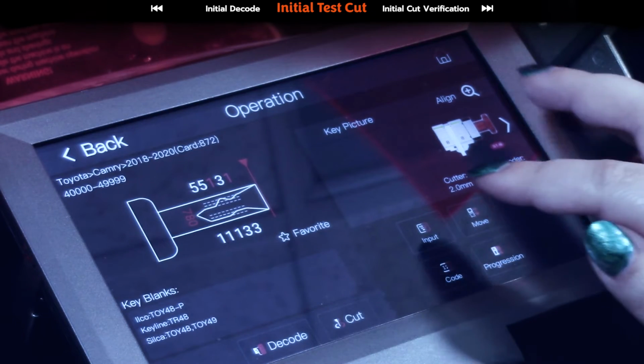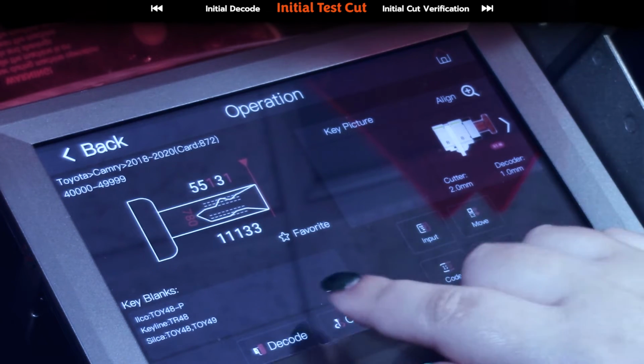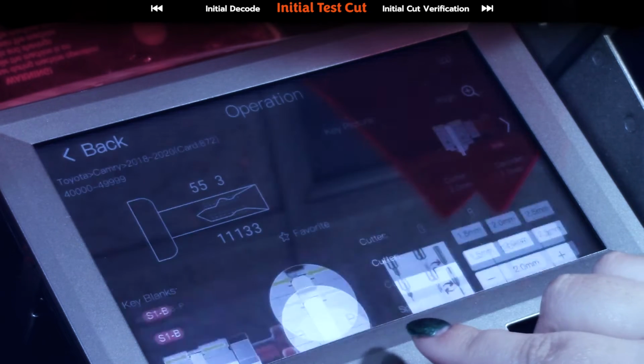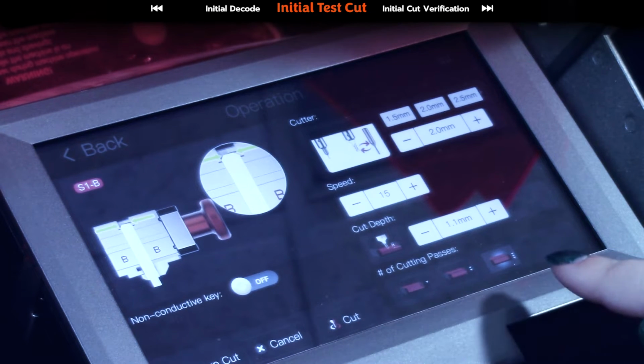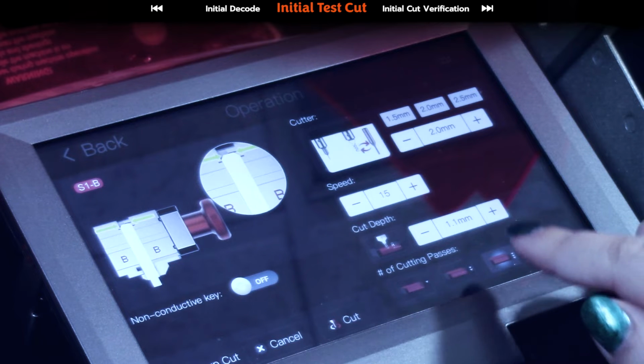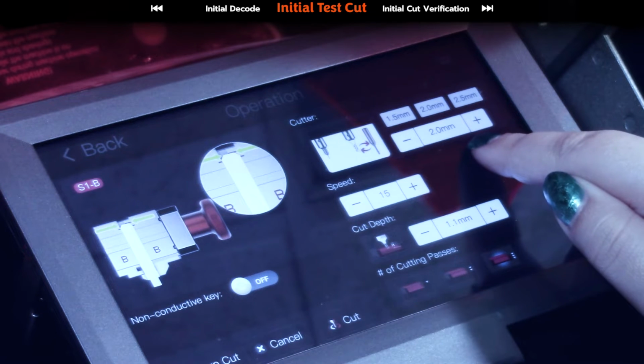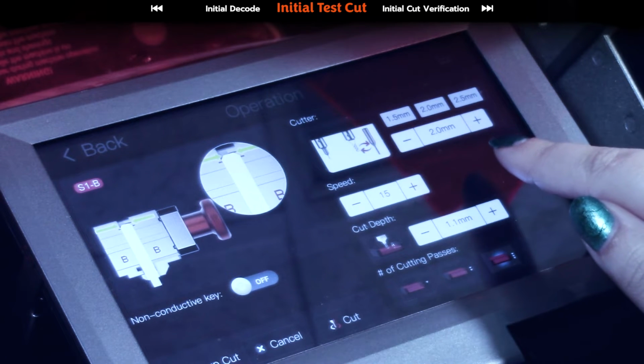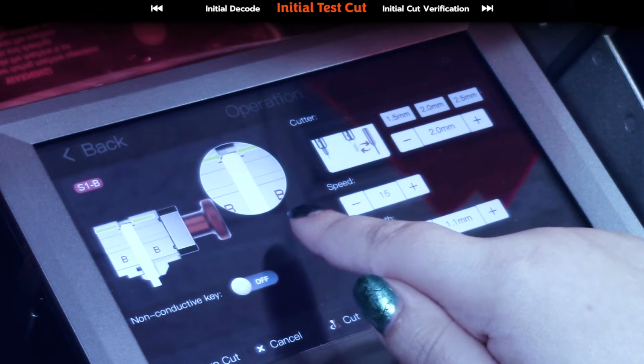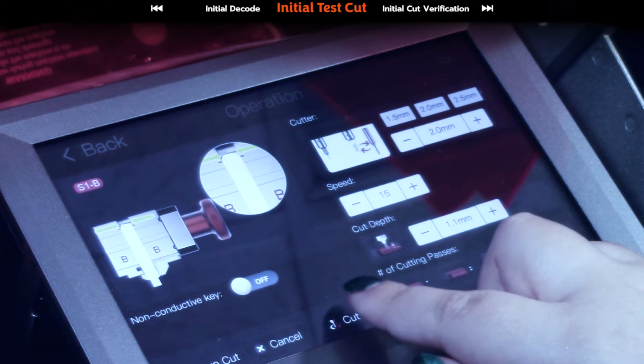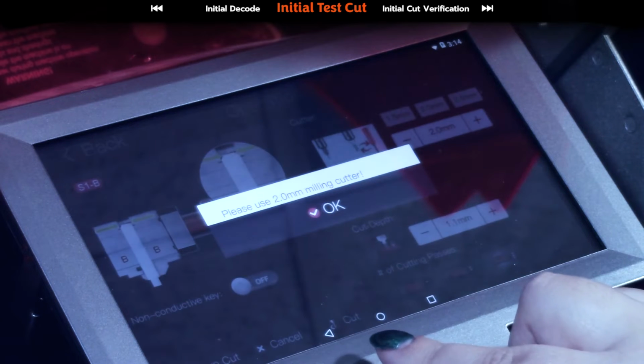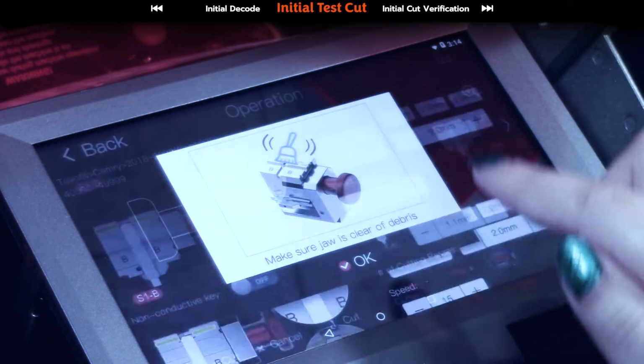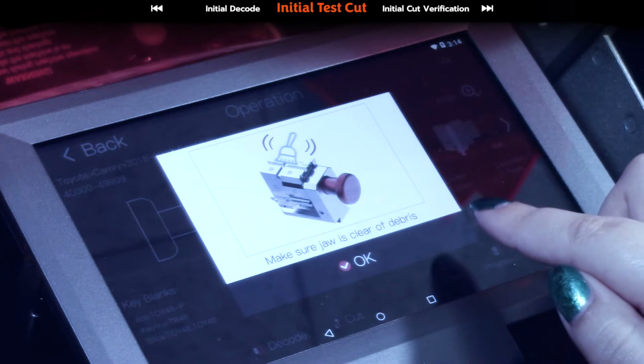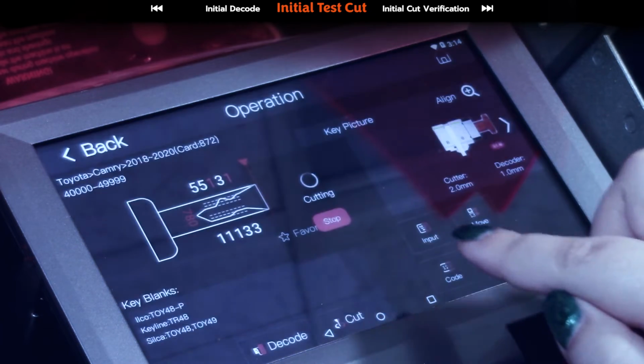Now we are going to look at the cut button here. And we are going to verify it shows 2.0 millimeter cutter, which we have installed. It's up to the second line on the B side. We're going to press the cut button now. Hit OK. No debris on the jaw surface. Hit OK.